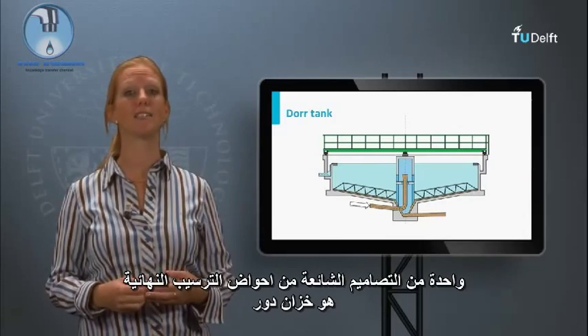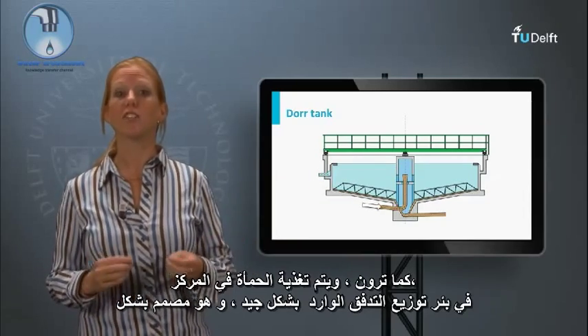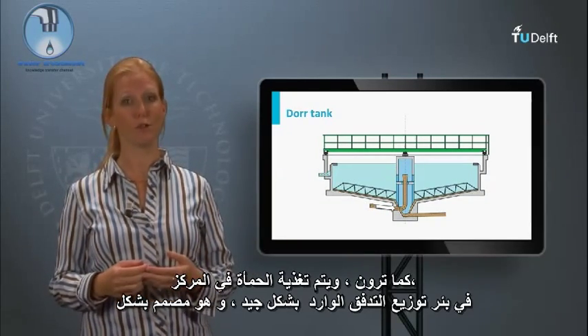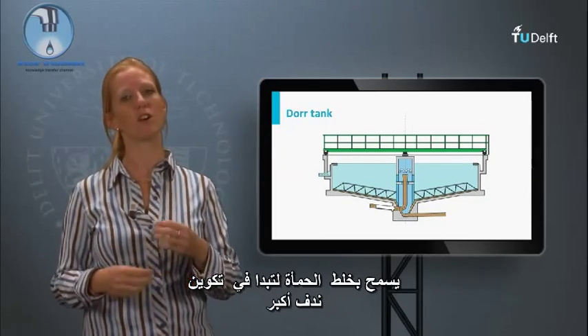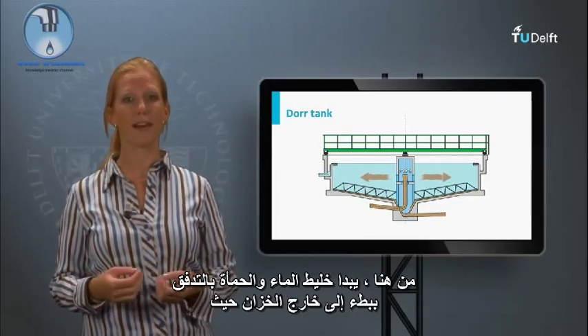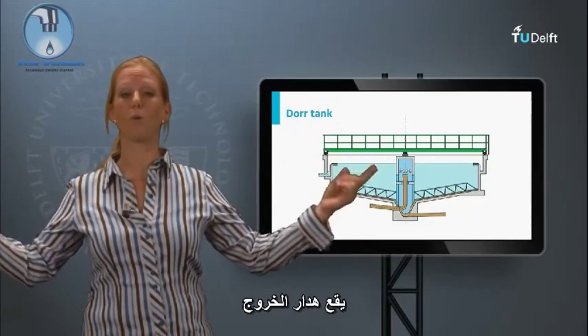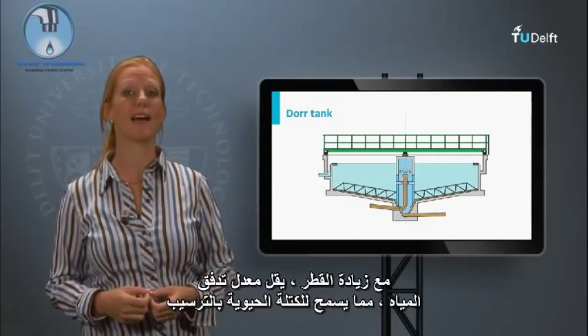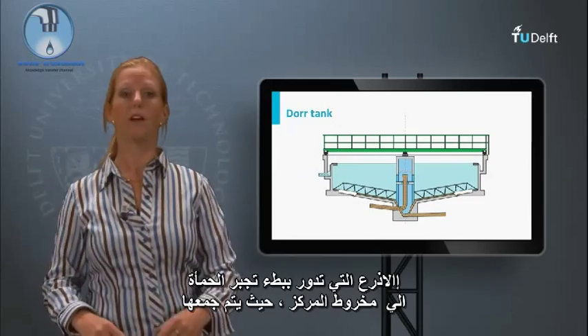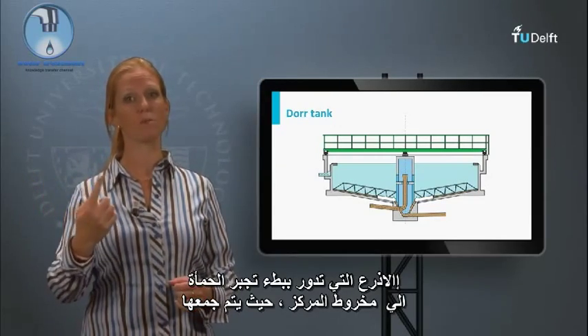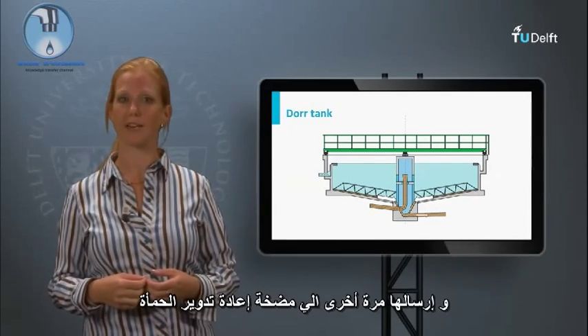One of the common designs of a round final clarifier is the Dorr tank. The sludge is fed in the center in an influent diffusion well, designed in such a way that the sludge is mixed and can start forming larger flocs. From here, the sludge-water mixture flows slowly to the outside of the tank, where the overflow weir is situated. With increasing diameter, the flow rate of the water decreases, allowing the biomass to settle. The slowly rotating arms force the sludge into the central cone, where it is collected and sent back to the recycling pump.